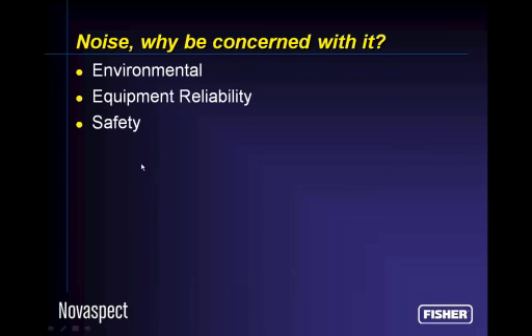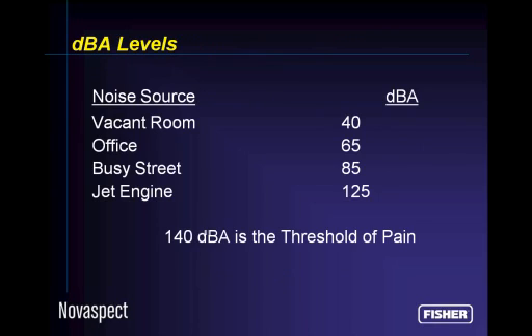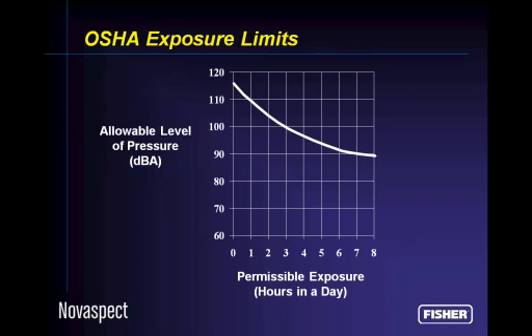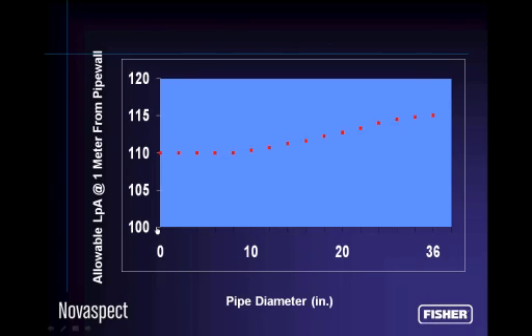Noise. We're concerned about that, of course. You've got environmental, equipment reliability, and safety issues going on. These are some examples of noise in the environment in which you live. There are OSHA exposure limits. You guys know all about these. This dictates what kind of hearing protection your operators in the field need to wear and how long they're allowed to be in the field being exposed to that level of noise. So something has to be done about noisy valves. Even if from an environmental, safety, OSHA, good neighbor policy standpoint, like I said, you don't find that there's a need to quiet a valve.